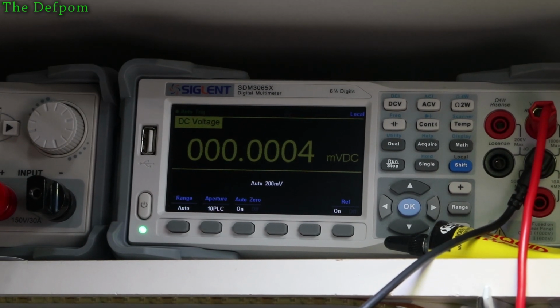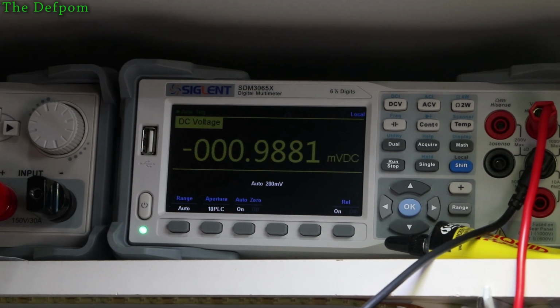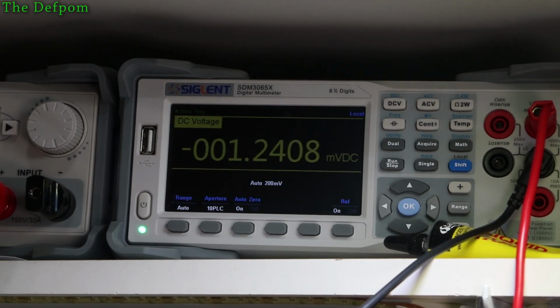So let's just move the probe off again, short them out. So that's shorted. Yep, that's good. So I'm pretty confident that's well within 2 microvolts, as per the manual. Put it back on. Yep, looking good. So I'm happy with that. That's the 2 adjustments done.